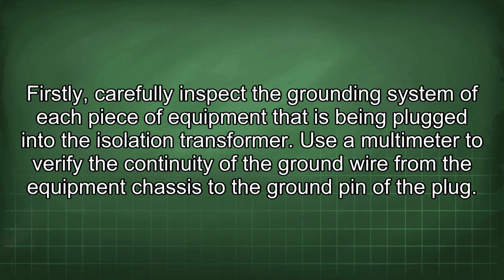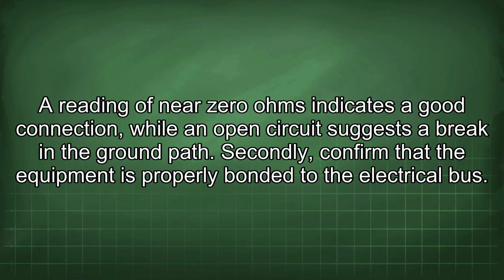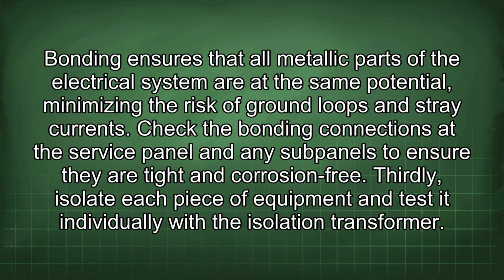Use a multimeter to verify the continuity of the ground wire from the equipment chassis to the ground pin of the plug. A reading of near 0 ohms indicates a good connection, while an open circuit suggests a break in the ground path. Secondly, confirm that the equipment is properly bonded to the electrical bus. Bonding ensures that all metallic parts of the electrical system are at the same potential, minimizing the risk of ground loops and stray currents.